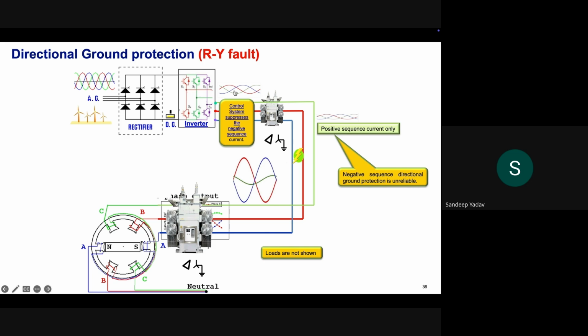However, in case of an inverter-based resource, in case of solar or a WTG wind farm, the total current fed will be positive sequence only, which will be very little different from the pre-fault currents. So for a phase-to-phase fault, we see that IR is equal to minus IY for a conventional generator. However, IR, IY, and IB are almost balanced when it comes to the fault response of a wind farm.